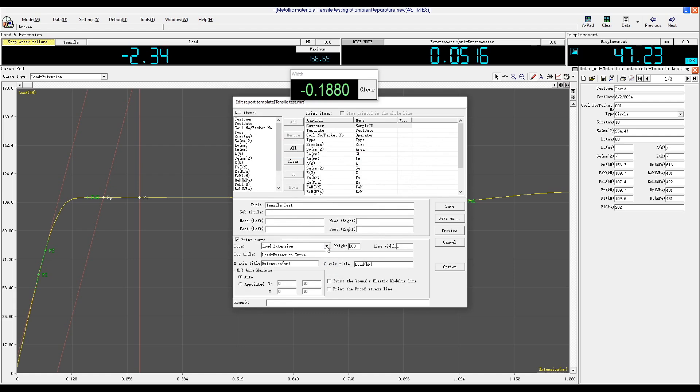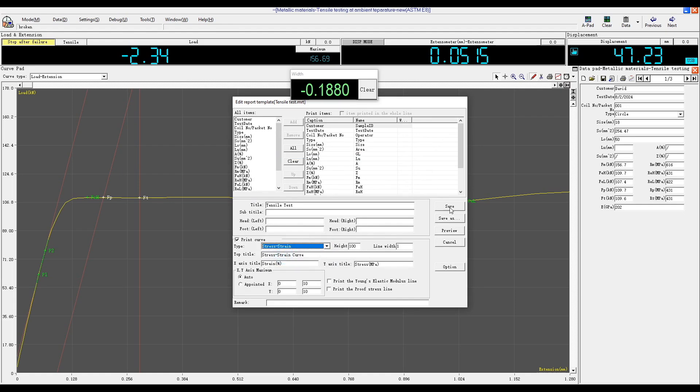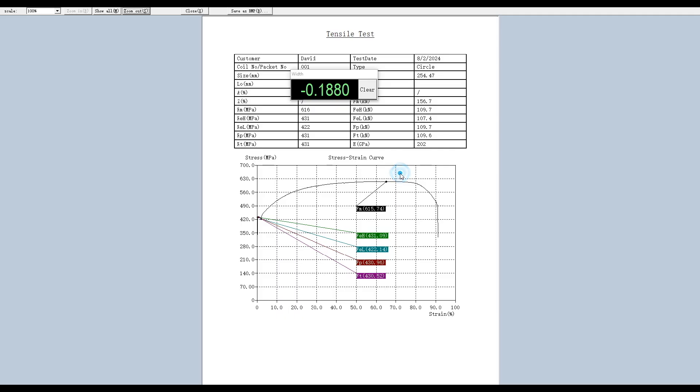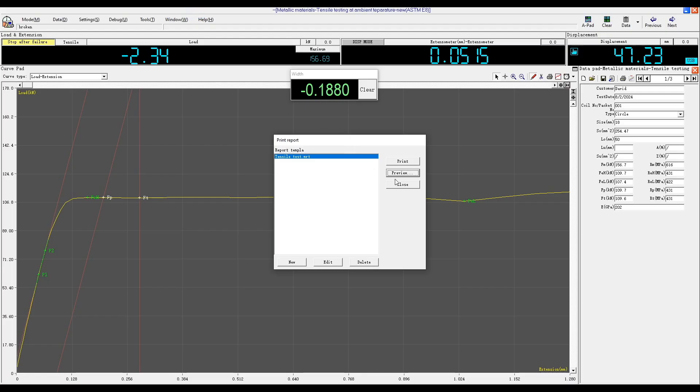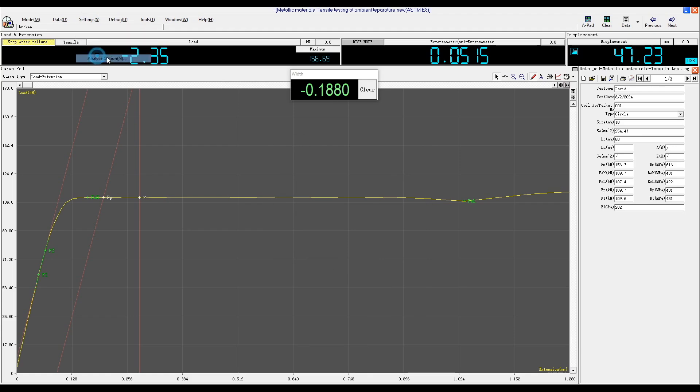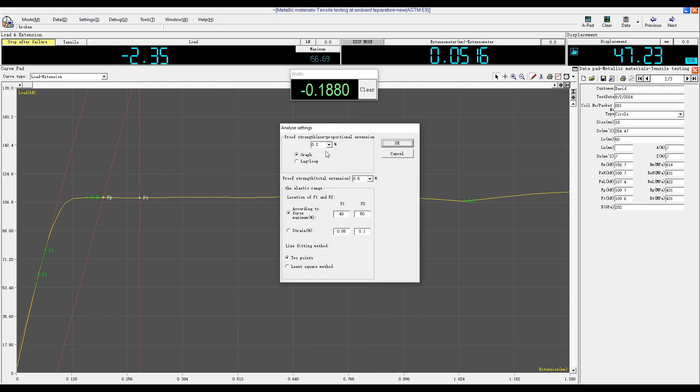Select an option from the drop-down menu. You may choose a proof strength setting, such as 0.1% or 0.2%. The P1 and P2 positions can also be adjusted. After making the changes, click Analyze Test Curve, and the RP value will change.